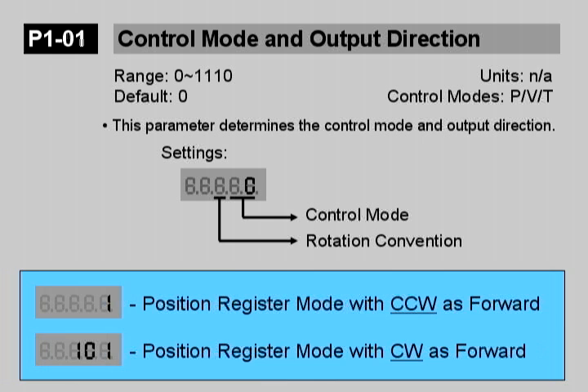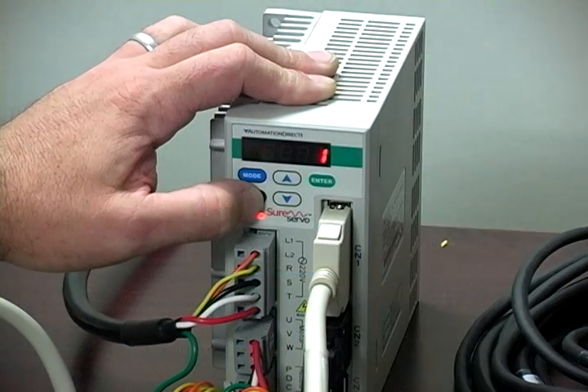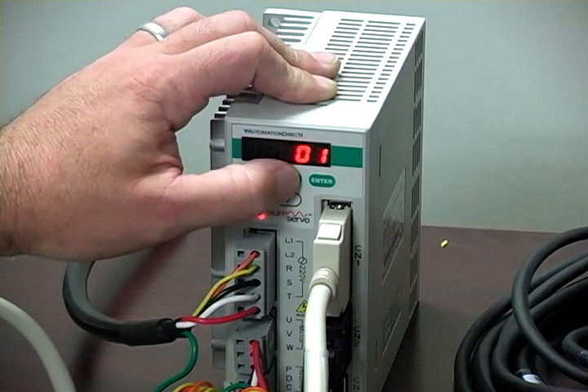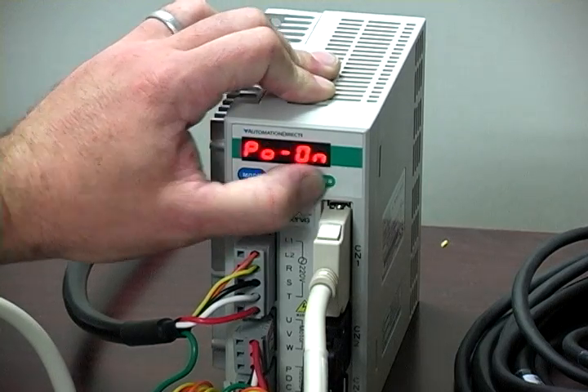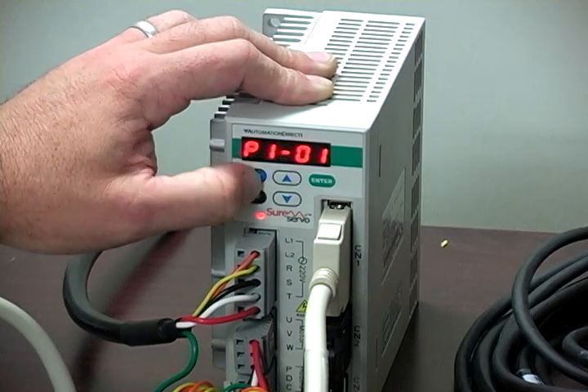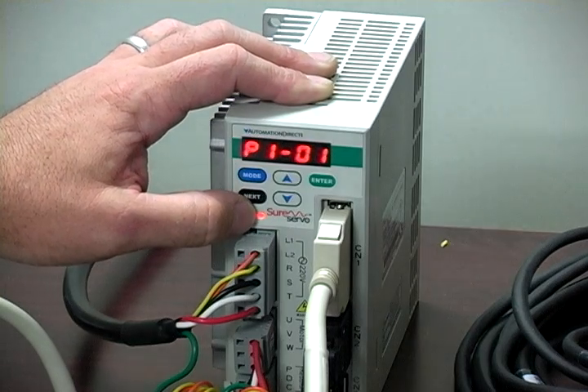Set the control mode first. P101 selects the control mode and direction. 0-0-0-0-1 will result in PR mode, that's position mode using the internal registers, with the motor spinning counterclockwise as forward. The second most significant bit sets direction. I'm going to use a setting of 0-1-0-1, which will also result in PR mode, but with the motor spinning clockwise as forward.